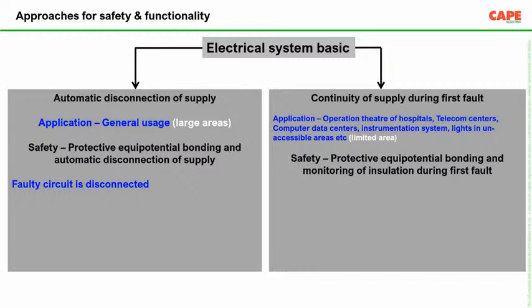Basically, you can set the insulation limit. Let us say at the start of the day the insulation is 10 megohm. You put a limit, say when the insulation is less than 2 megohm, because the insulation keeps reducing and degrading over a period of time. Once the insulation reaches a certain limit, the device will give you an indication. Either it will give an alarm or some other indication so that you can take care of the system.